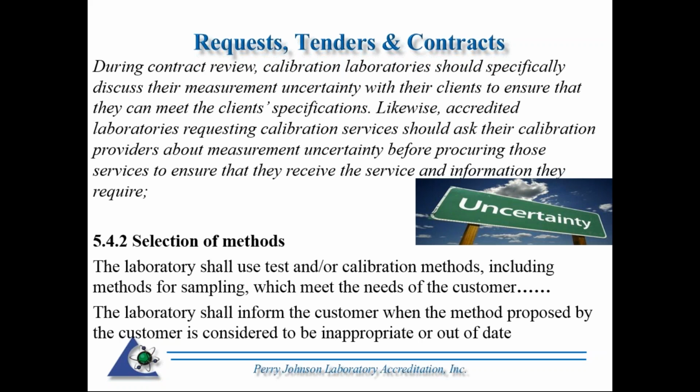Again, 5.4.2 is mentioned within section 4.4. 5.4 is the calibration method, testing method, and method validation section. It states the laboratory shall use test and/or calibration methods, including methods for sampling, which meet the needs of their customers. Also, the laboratory shall inform the customer when the method proposed by the customer is considered to be inappropriate or out of date.